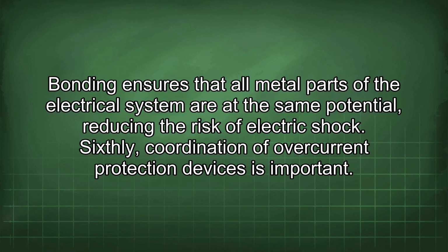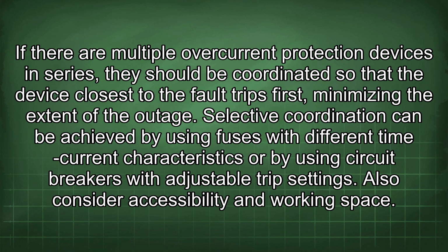Bonding ensures that all metal parts of the electrical system are at the same potential, reducing the risk of electric shock. Sixthly, coordination of overcurrent protection devices is important. If there are multiple overcurrent protection devices in series, they should be coordinated so that the device closest to the fault trips first, minimizing the extent of the outage.